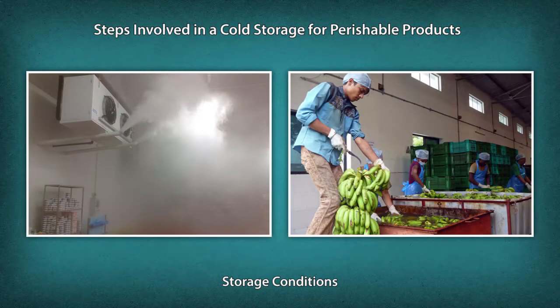Relative humidity. For most produce, a high but not saturated relative humidity is required, around 85 to 95%. This can be achieved by sprinkling the produce with water or dipping it in water, and this should be done before storage. If the vegetables are sprinkled during storage, condensation occurs at the refrigeration unit.